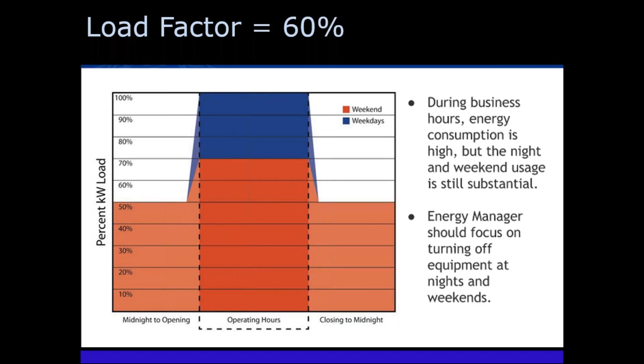If you see a load factor around 60 and you're looking to save energy, you'd want to reduce these areas, since it shows they're not turning things off. We haven't even been to the building, just looked at the bills, but the load factor tells you where to look for things to turn off. That's what load factor analysis lets you do.